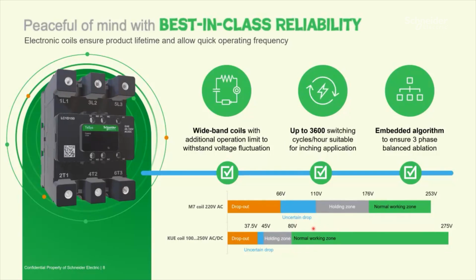The second advantage of having an electronic coil is that you get more switching cycles. If your operation is inching operation for hoisting for cranes, you will need a lot of operations within an hour. This contactor can be operated for 3600 switching cycles in an hour. The existing contactor was capable of handling 2400 switching cycles, and a lot of competitors cannot even manage 1200 switching cycles. So this contactor can offer you 3600 switching cycles, not only for hoisting applications, but you can use it for welding applications too. And finally, this contactor is an intelligent contactor.